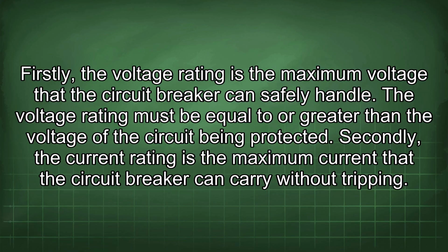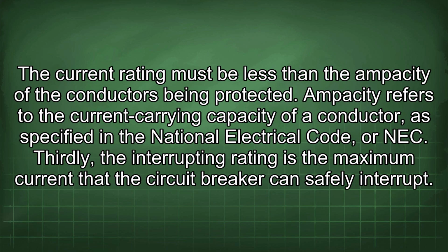Secondly, the current rating is the maximum current that the circuit breaker can carry without tripping. The current rating must be less than the ampacity of the conductors being protected. Ampacity refers to the current carrying capacity of a conductor, as specified in the National Electrical Code, or NEC.